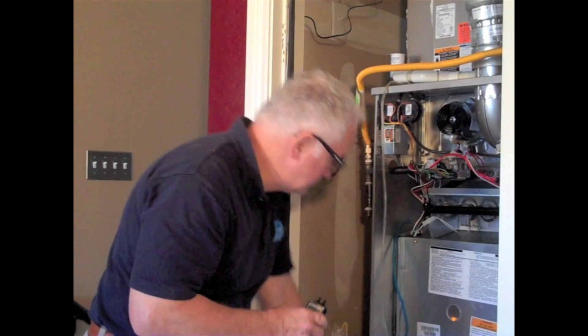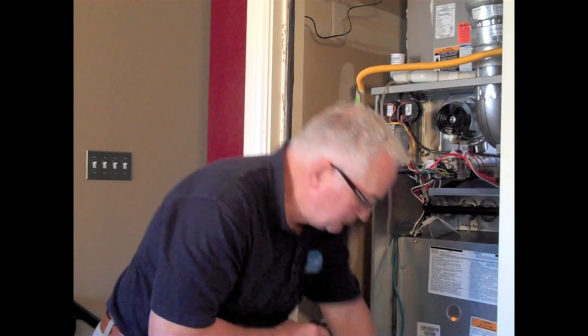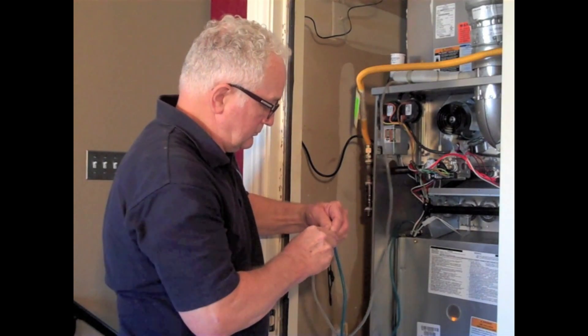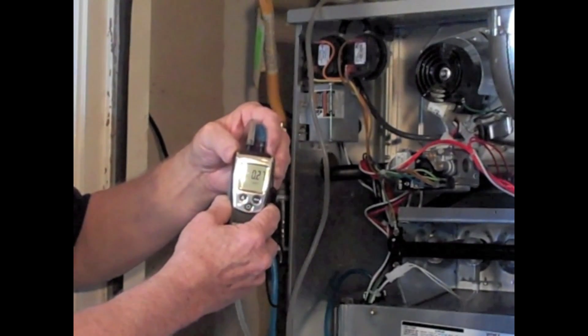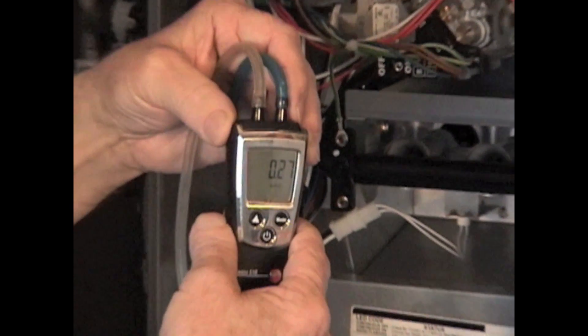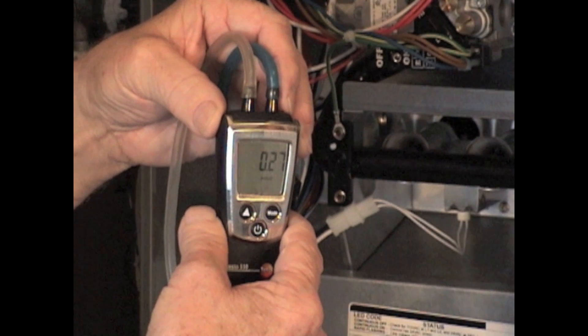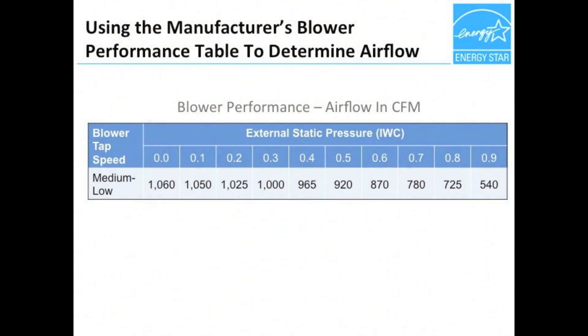Rob has already connected the tubing to the probes and turned on the HVAC system so that the fan is operational. He can now measure the external static pressure by connecting the tubing to the manometer. Here we see the results for the total external static pressure test, with both probes connected to the manometer. The total external static pressure of the system is 0.28 inches water column (IWC). Rob can now determine the airflow of this fan using the blower performance data from the manufacturer. Knowing that the fan was set to the medium-low setting and the measured external static pressure is 0.28 IWC, the airflow is between 1025 and 1000 CFM. By interpolating, we get a final airflow of 1005 CFM.